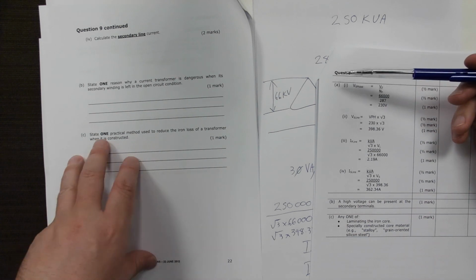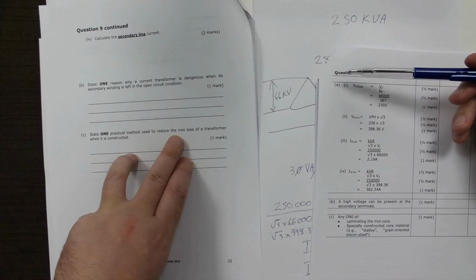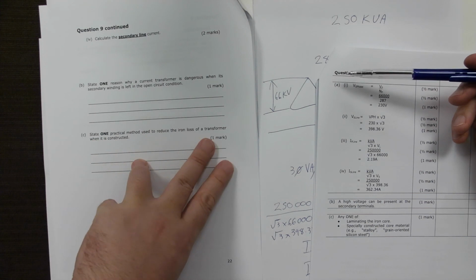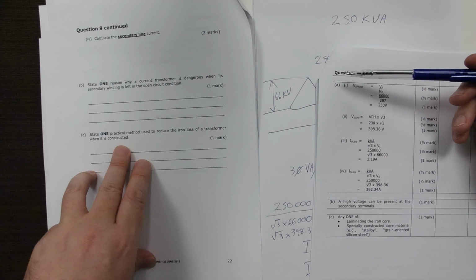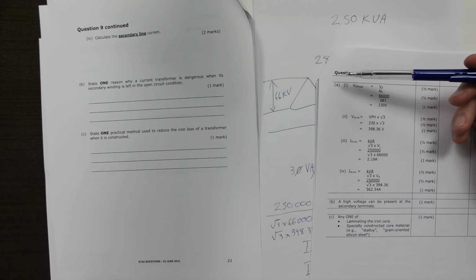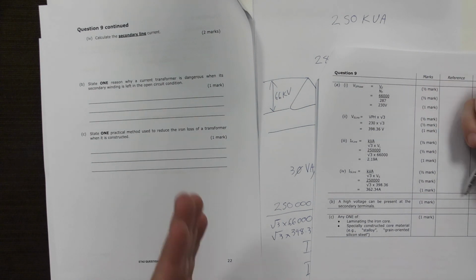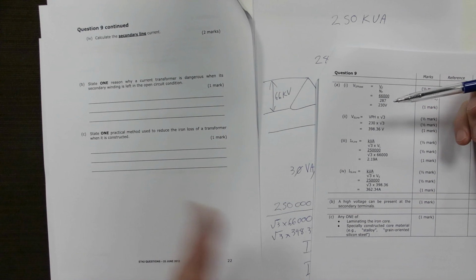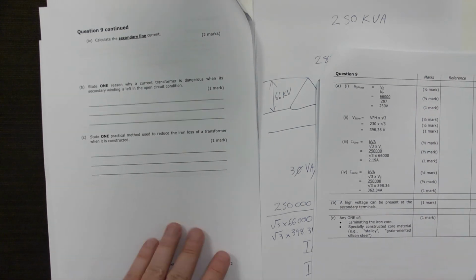And then state one practical method used to reduce the iron loss of a transformer when it is constructed. And so this is where we laminate the iron cores so that we don't have the eddy current going through them. And we also use special types of steel, such as silicon steel, which has a very high internal resistance, once again reducing those eddy currents. And that is the end of question 9.